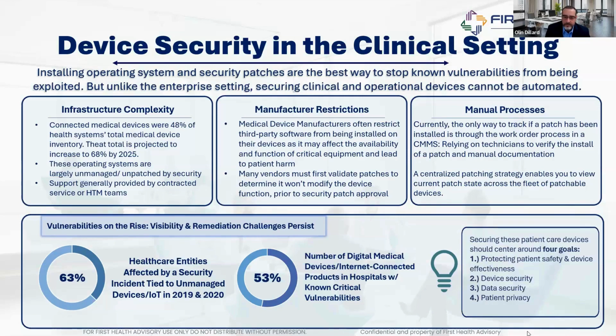In the medical domain, patches must be validated by the MDM. You cannot simply take whatever the OS vendor makes available and apply it in a safe way. Validated patch approval from the manufacturers is frequently not easy to obtain. And what is approved for install varies greatly between device models and is difficult to track in the CMMS, as I mentioned earlier. So without a centralized patching strategy or solution for IoMT, it's difficult to document. It requires technicians to be in front of the devices with external storage to apply patches. It's difficult and inefficient to track down devices needing updates. And potentially the skill sets of biomed technicians within these departments may not allow them to install these patches.